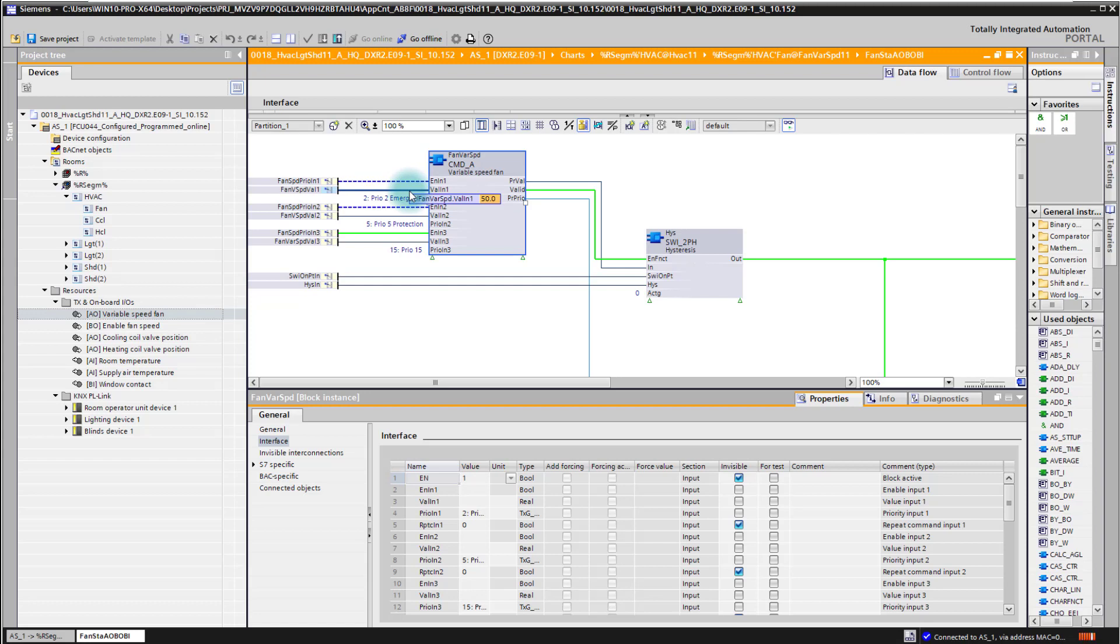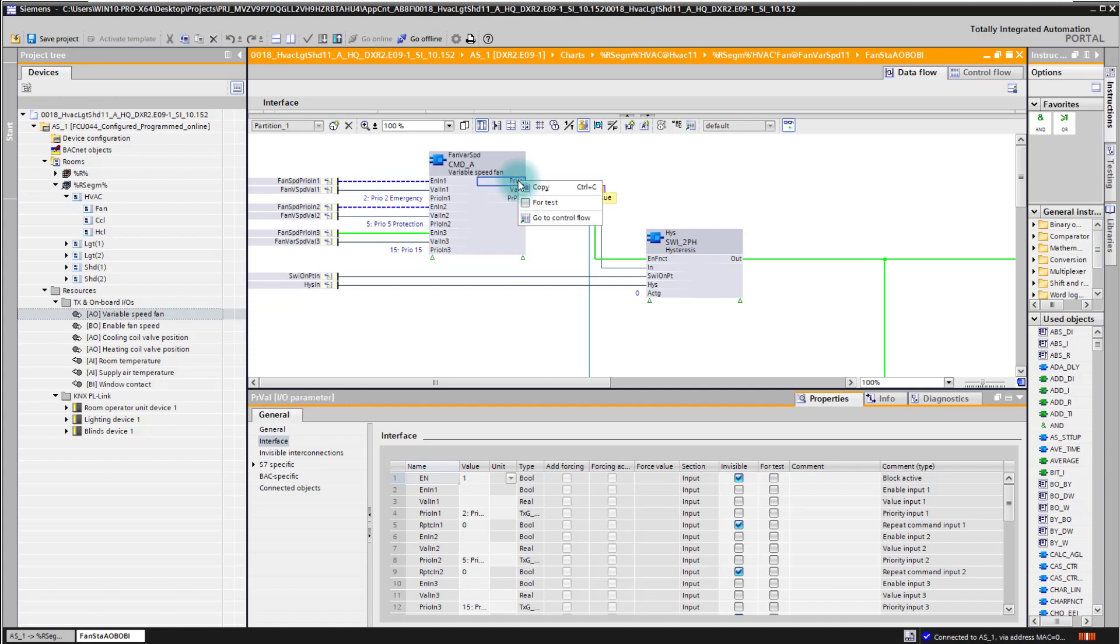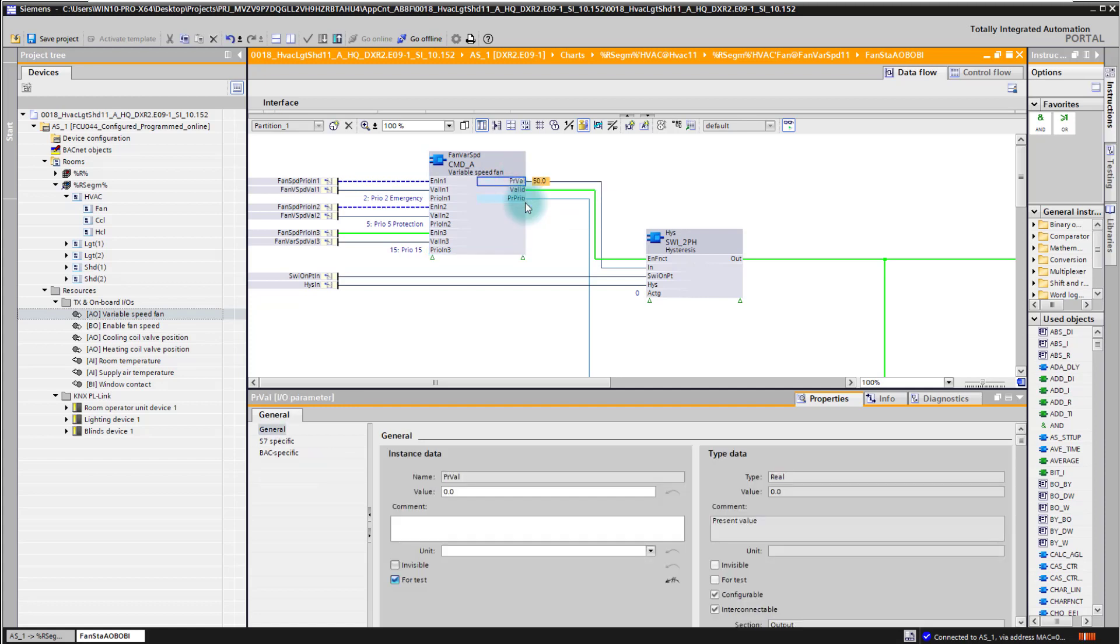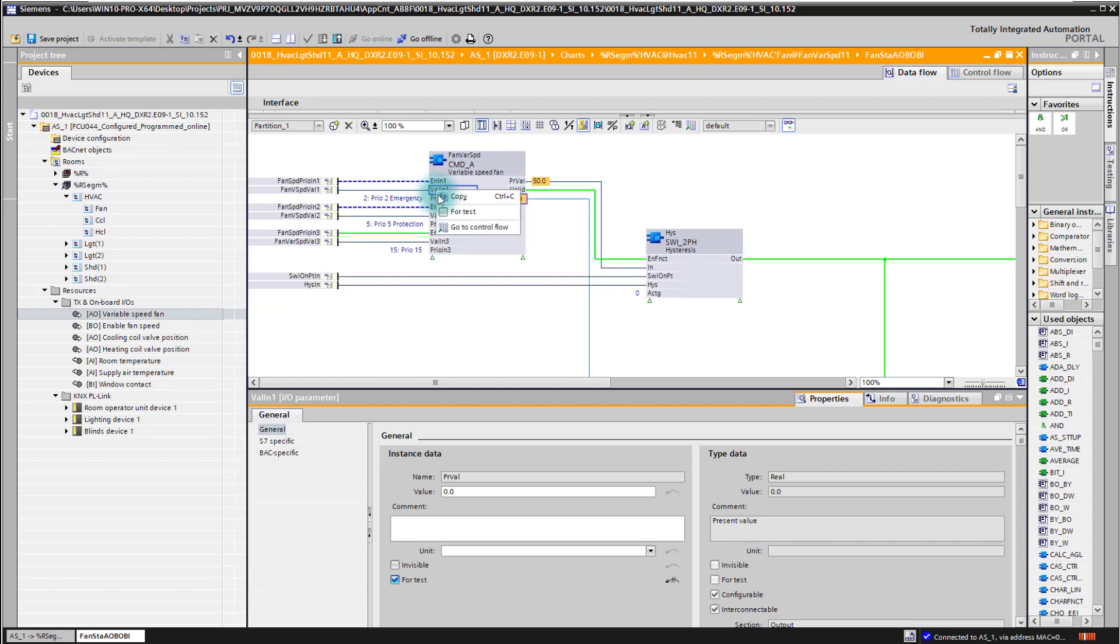I can also change the visibility of the online value on a pin. So for example, here on the input of the process value I can do a right click, say go for test, and then I see here that value always visible even if I go to another value. I can do that also on a couple of pins, always to say okay go for test, and then the value always remains as it is.